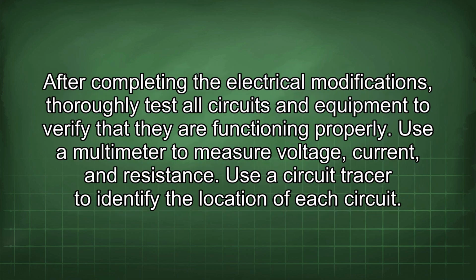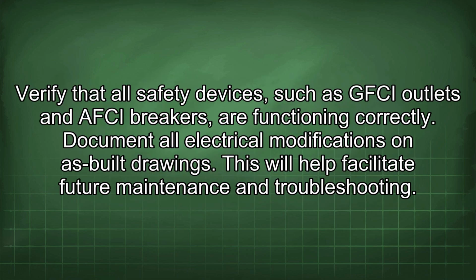After completing the electrical modifications, thoroughly test all circuits and equipment to verify that they are functioning properly. Use a multimeter to measure voltage, current, and resistance. Use a circuit tracer to identify the location of each circuit. Verify that all safety devices, such as GFCI outlets and arc fault breakers, are functioning correctly.